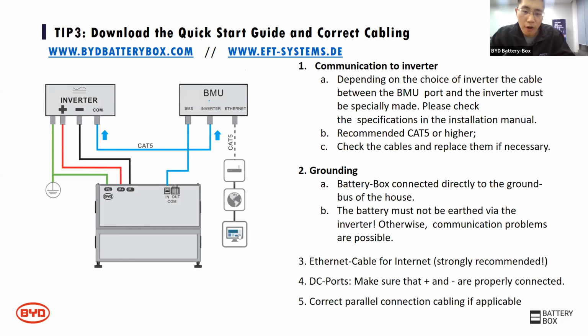Another important point for low voltage is the cable connections. Communication to inverters depends on the choice of inverter, and the cable between the BMU and the inverter must be specially made - please check this. A Cat5 or similar cable is recommended; check the cables and replace them if necessary. Also, a grounding cable is required, and the battery box must connect directly to the ground bus of the house.